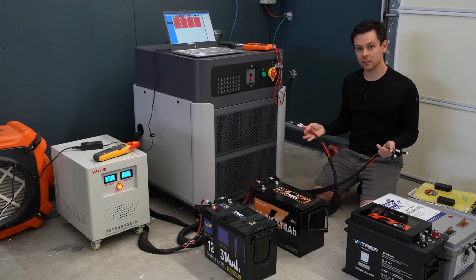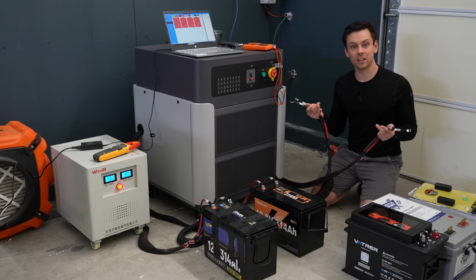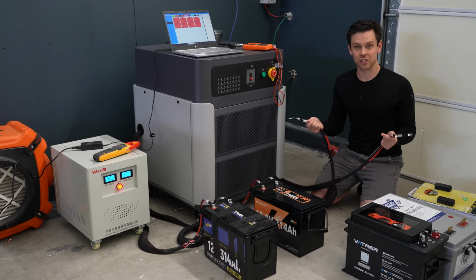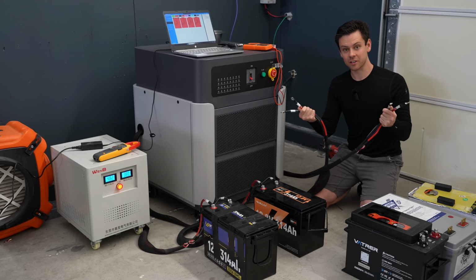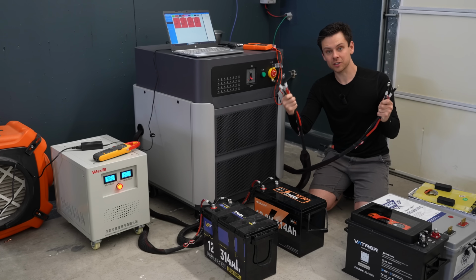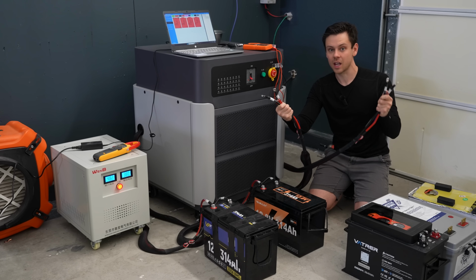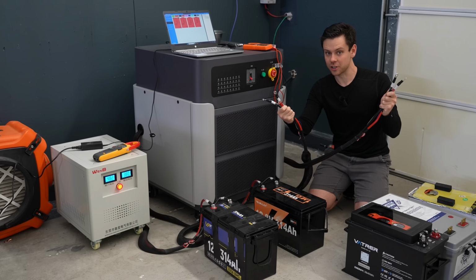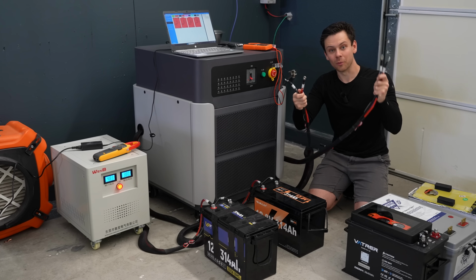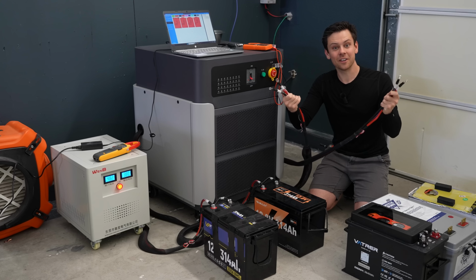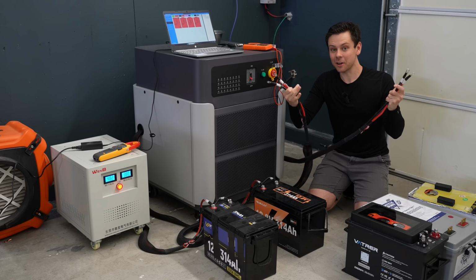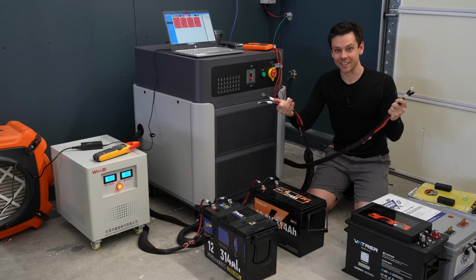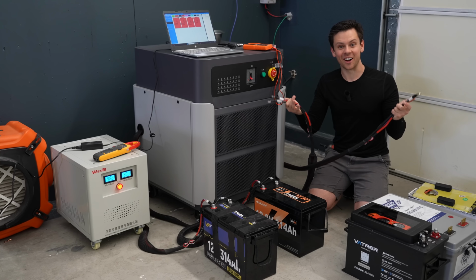Most electronic loads and cycle machines generate a lot of heat and take a lot of energy, but this one is actually regenerative. So if we have 2 channels and one is charging with 100 amps and the other is discharging with 100 amps, this machine will move the energy from one battery to the other instead of converting it to heat. This is about 10 to 20 times more efficient, which means I can actually run this off of solar.